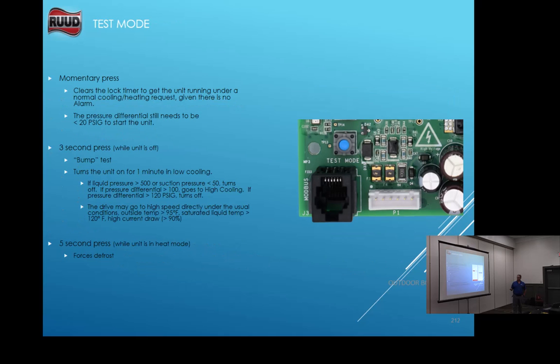This is our test mode. You can come in here on this test mode on the button here. If you press it real quick, it will clear any time delays that you have on the board, except for one. This is where we're talking about the high compressor. Which one do y'all think it won't clear? That pressure differential. If it's still got greater than 20 psi differential between suction and discharge, it will not clear that alarm. It'll still keep it shut down until it equalizes.